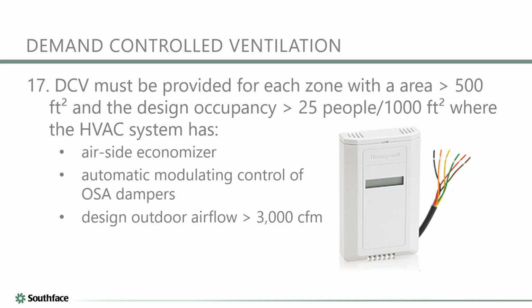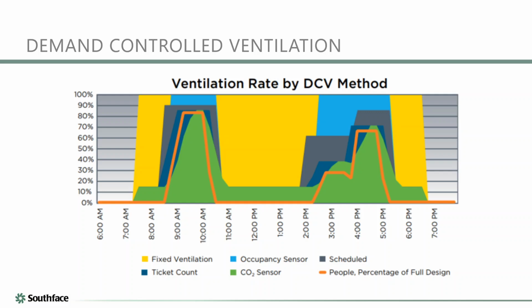And here we have a graph that shows various techniques of bringing in ventilation. I think you can see in that background, that yellow color, that's just fixed ventilation turning on at about 7 o'clock, turning off at about 7 o'clock, running at full blast that whole time. That's probably not going to be very efficient. So you have various other methods that are more and more efficient, but if you look at the foreground, you see that green color, that's going to be your CO2 sensor, which looks to be pretty much the most efficient because it's going to run that ventilation only when you need it. And that's really the key of demand-controlled ventilation.